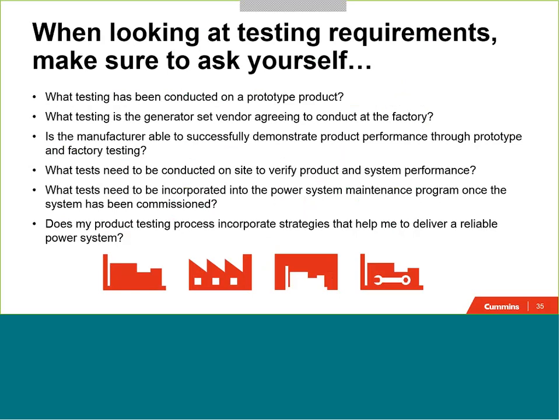And also look for the opportunity to engage in witness testing. It really gives you an opportunity for a hands-on touch with the product before it ever leaves the manufacturer's facility. Oftentimes, issues with generator sets are typically found within the first couple hours of operation of the product, and so an extended run on a larger project may help you to catch some of these issues ahead of time.